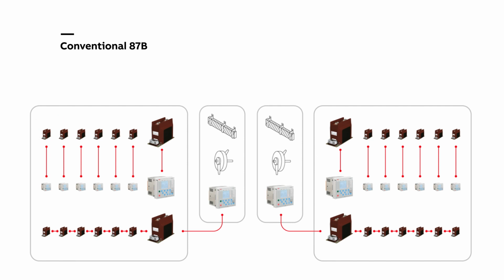You also need an additional set of conventional CTs that are sending the analog signals from the panels together to one special 87B relay using conventional wiring. You further need to select the right varistors and stabilization resistors for the 87B relay itself. For a double section, you will need to have it doubled.